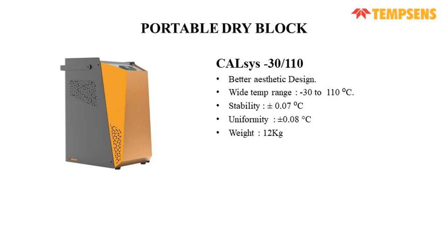Next, we have CALsys -30/110. The temperature range for this calibrator starts at minus 30 centigrade, with stability of plus minus 0.07 degrees centigrade and uniformity of plus minus 0.08 degrees centigrade. And the weight of this calibrator is 12 kg.